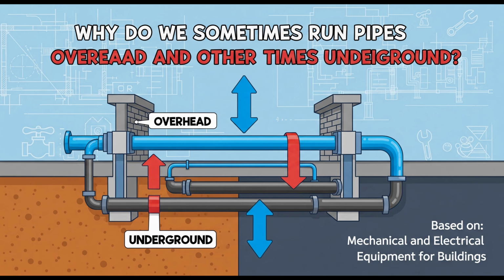But then, of course, you need to cover them up to create a level floor finish. Right, you can't just leave pipes exposed on the floor. Exactly. So this method requires adding a fill, usually concrete or sometimes a lighter material, typically about 5 or 6 inches, maybe 125 to 150 millimeters deep, over the pipes. This covers everything and gives you a surface for your final flooring, like tile or carpet. The trade-off, it directly impacts the finished floor height. You lose 5, 6 inches of ceiling height below, or the whole building has to be designed slightly taller from the start. It needs careful planning between the architects and engineers right from the beginning. So you're trading ceiling height or overall building height for concealed pipes within the floor structure.